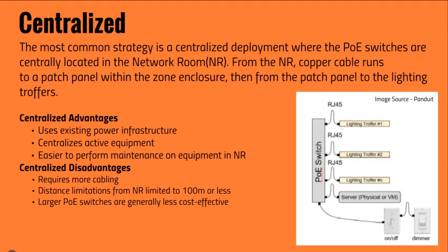Centralized architecture: the most common strategy is centralized deployment, where the PoE switches are centrally located in the network room. From the network room, copper cable runs to a patch panel within the zone enclosure, then from the patch panel to the lighting troffers. Centralized architecture advantages are: it uses existing power infrastructure, it centralizes active equipment, and it is easier to perform maintenance on equipment in the network room.